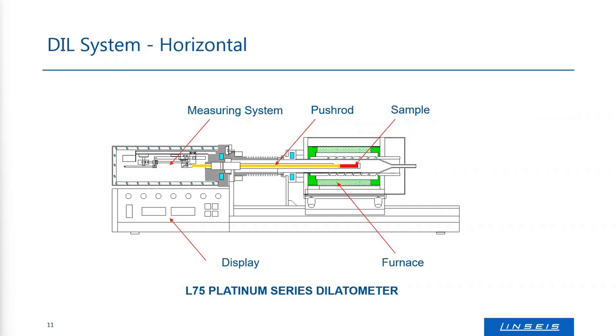Here is a schematic drawing of one of our dilatometers. What is used here is a pushrod, the yellow part, which is in contact with the sample. Whenever the sample is expanding or shrinking, this pushrod moves into the measuring system. The dimensional change of the sample can be monitored very sensitively, down to the nanometer range.